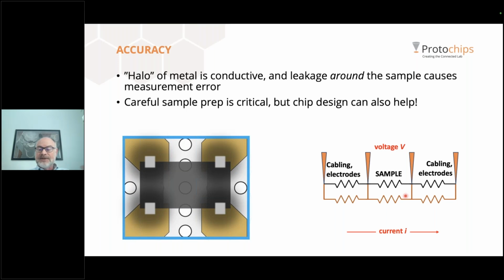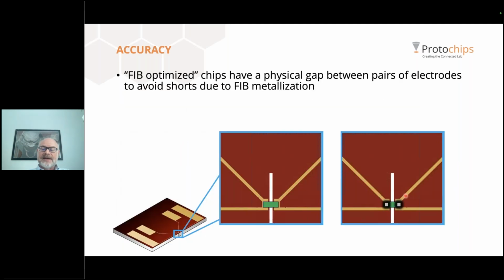You can actually change the metal deposition conditions completely to mitigate this somewhat. Sometimes you can make your FIB cut larger, and this is now even more possible due to the rise of plasma FIBs that are faster and cleaner. But one interesting solution comes down to chip design. As I mentioned earlier, we offer electrical E-chips without a membrane. So there's a physical gap between pairs of electrodes, and deposited metal can't span across that gap. The notch is long enough so that it extends beyond a halo completely. And this is a real advantage for FIB users since you can mount, form contacts, thin in place, and image at high resolution. Another solution lies with avoiding FIB metal altogether.